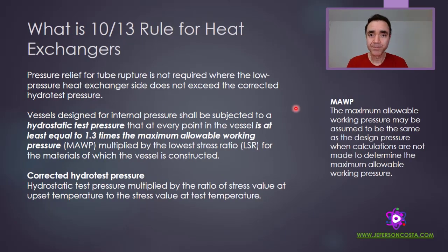What does API 521 say? API 521 says that pressure relief for tube rupture is not required where the low pressure heat exchanger side does not exceed the corrected hydrotest pressure. When we have a shell and tube heat exchanger, for instance, we have the process fluid and we have the cooling or heating fluid. And these fluids can operate at different pressures.